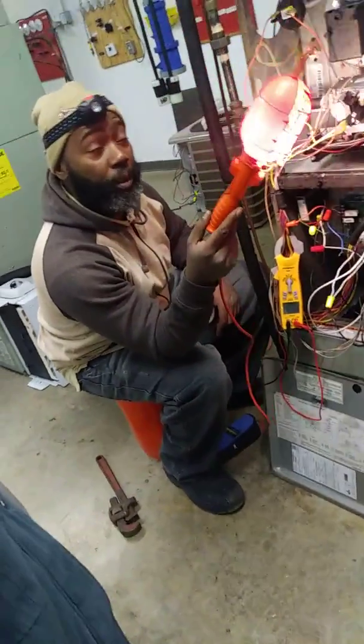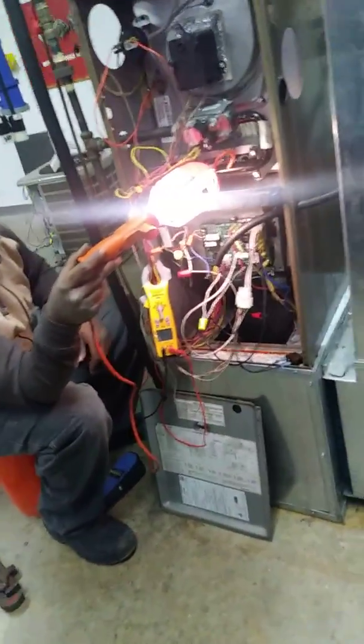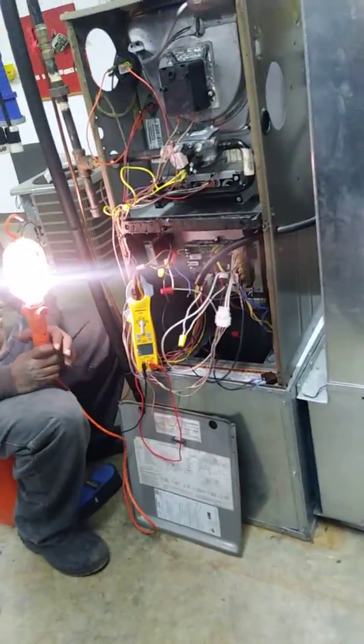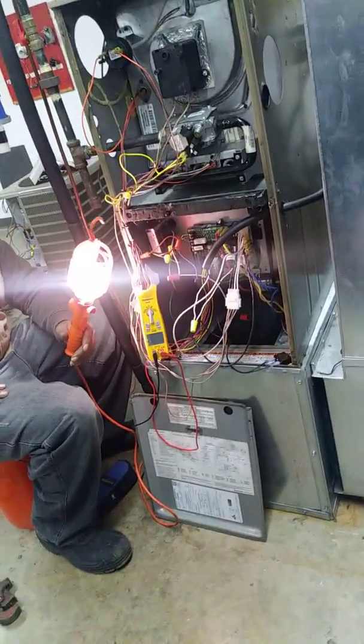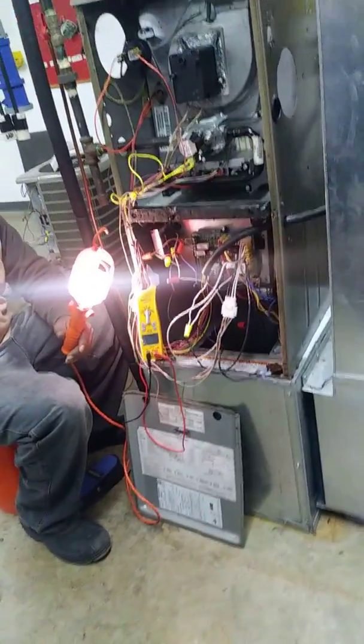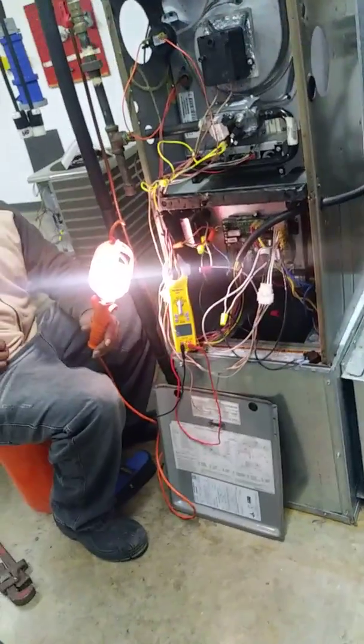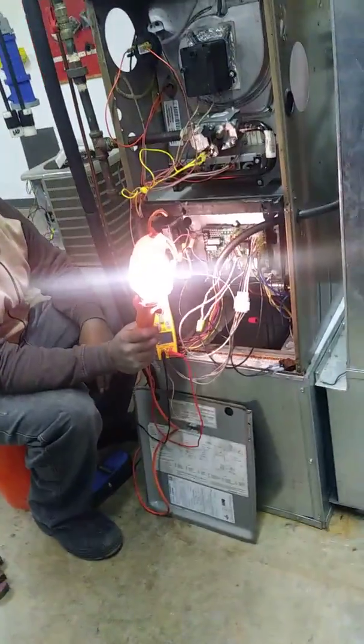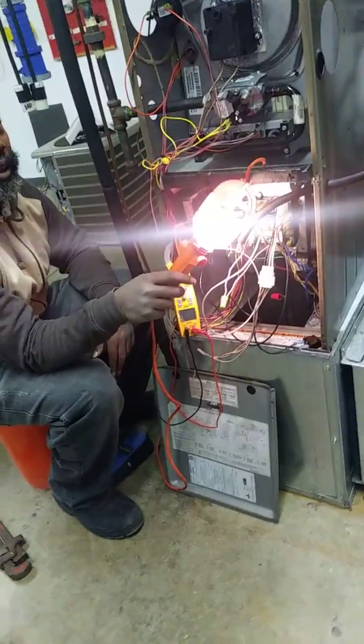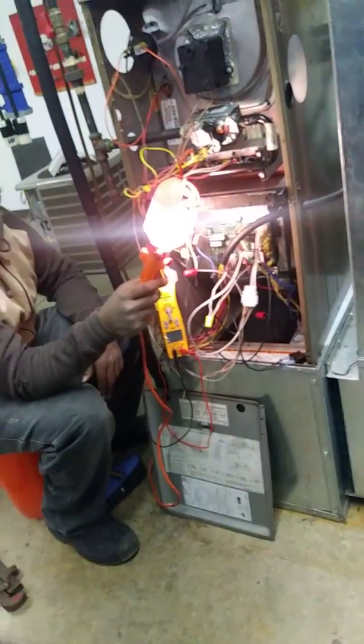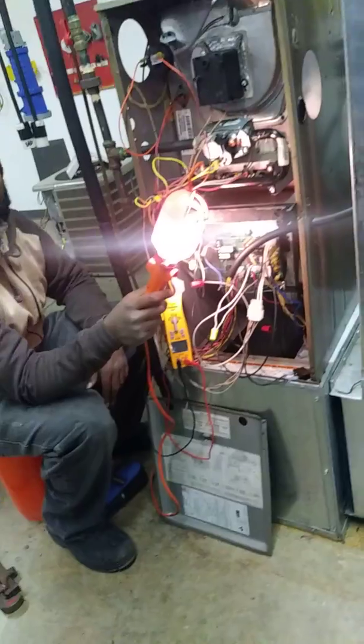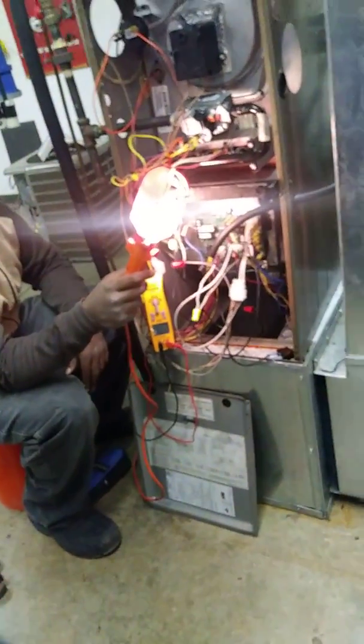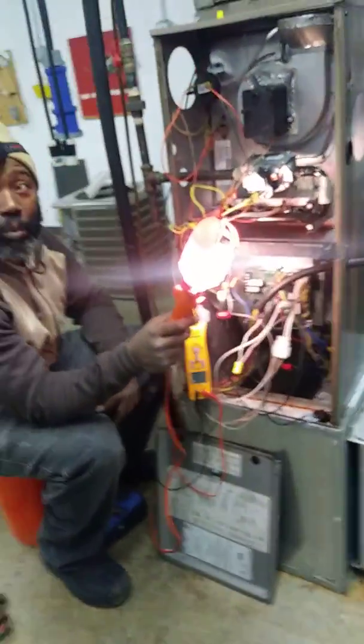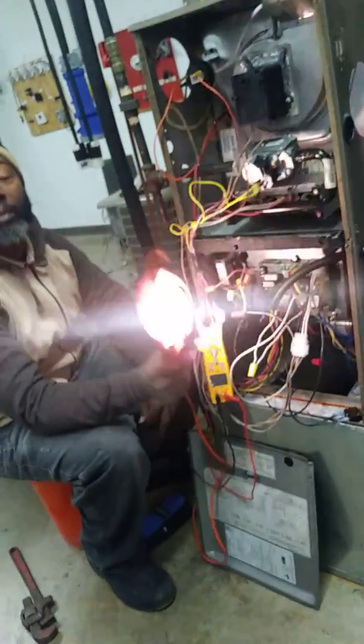Yeah, but it's going through the whole sequence. It's giving you the hot surface ignition. Like you say, you can plug this into an outlet without even having gas, and you should get all the way to the hot surface igniter, and the gas valve should click, and then it shuts down. So what if the fire goes on for a bit, and then it turns off? What's a bit? A few seconds to a minute.